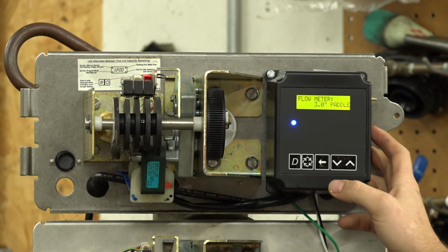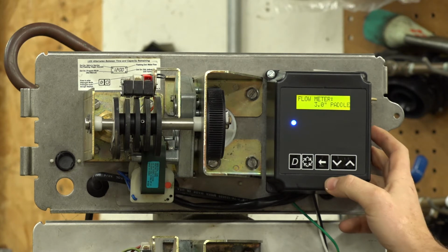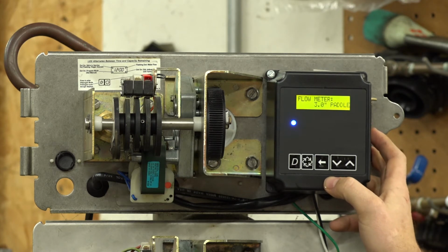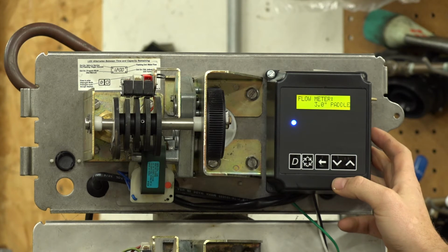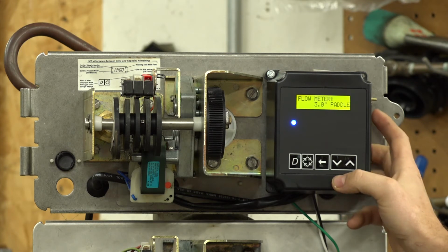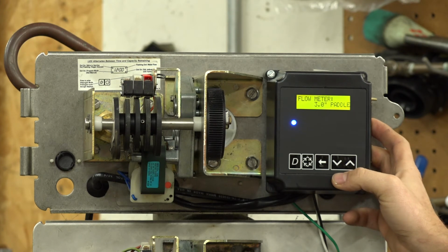All electronic meters, basically what they do is there's a signal sender, a magnet or whatever, that's turning, and each time it turns by the pickup, it sends a pulse. So some of them, the Clack 2-inch meters, maybe I'm wrong on this, are 20 pulses per gallon. So every time that turns 20 times, that's 1 gallon of water. That's why we have to set it for pulses. It counts then. So 40 pulses, 2 gallons. And that's the reason the pulse per gallon is so important.